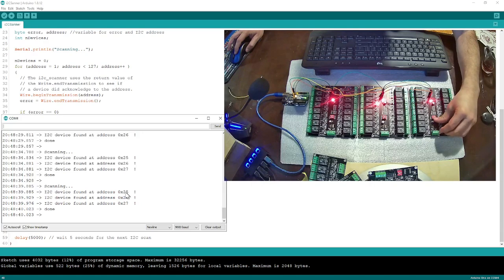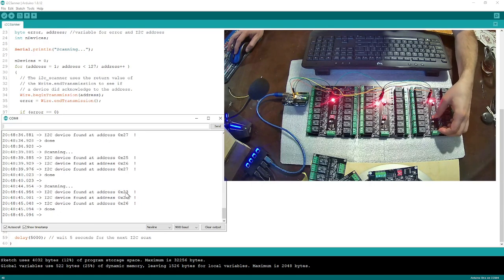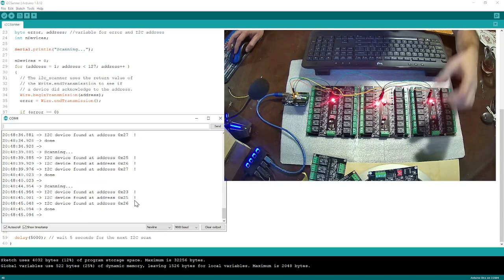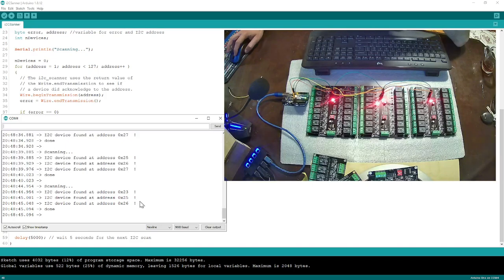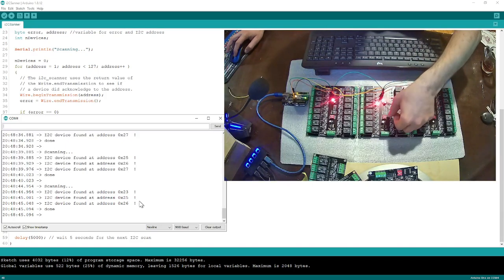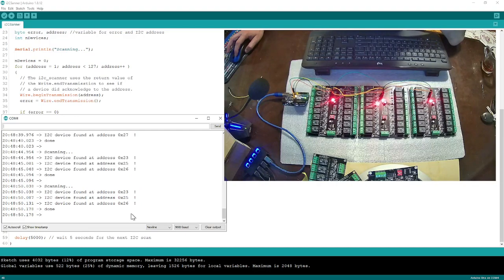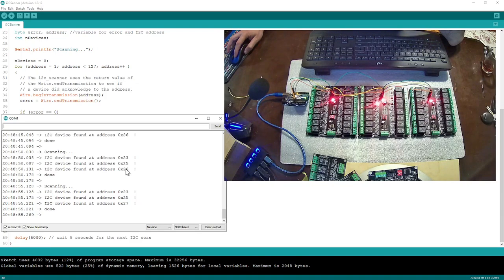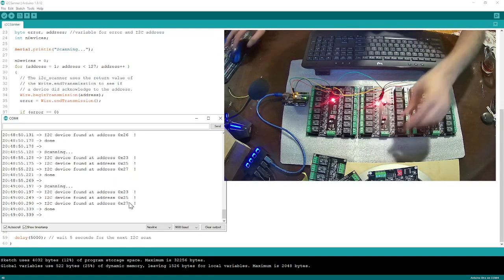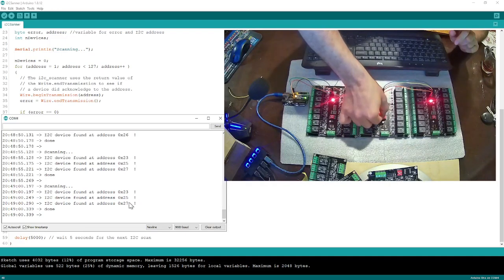I'll do the same thing on the second board — I'm going to flip switch number three all the way up. As you can see, the second board's address changed from 26 to 27. Now I'll put it back down.